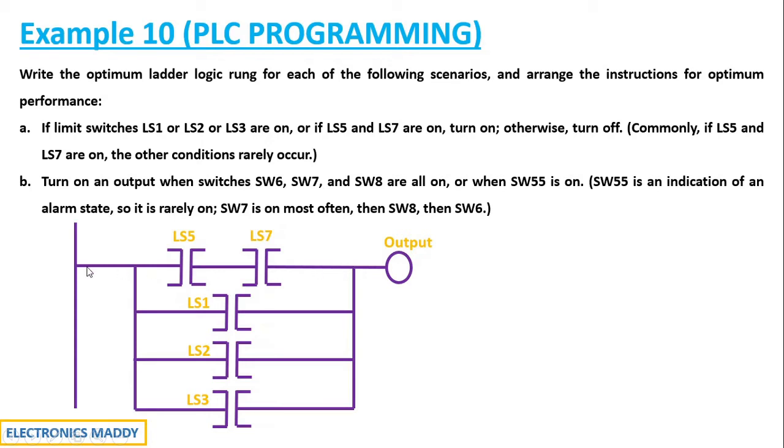If this is true, automatically the output will be high. In that case, it will reduce the amount of time required to check the scans. It doesn't have to check LS1, LS2, LS3. Each of the rungs need not be checked. Only the first rung if it is checked, it is more than enough and that is why you will have an optimum ladder logic.